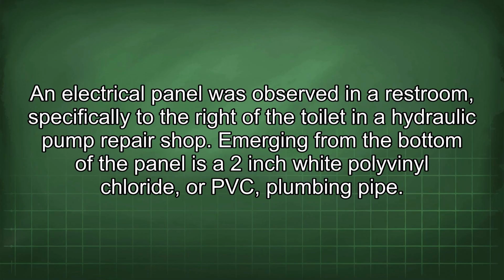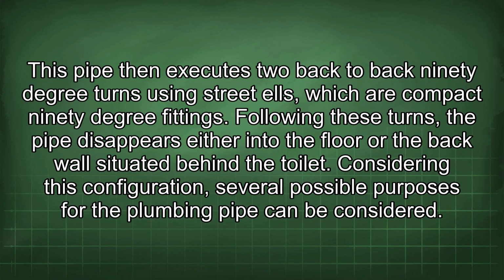An electrical panel was observed in a restroom, specifically to the right of the toilet in a hydraulic pump repair shop. Emerging from the bottom of the panel is a 2-inch white polyvinyl chloride, or PVC, plumbing pipe. This pipe then executes 2 back-to-back 90-degree turns using street ells, which are compact 90-degree fittings. Following these turns, the pipe disappears either into the floor or the back wall situated behind the toilet.